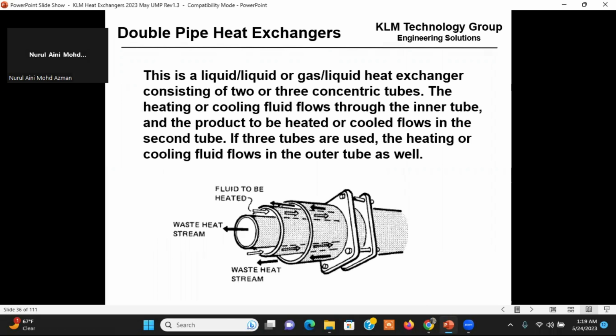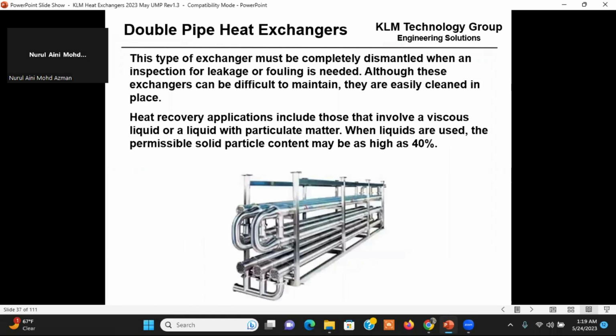A double pipe heat exchanger looks like this. The waste heat stream, the stream that has the heat, is kind of counter current, and it flows in separate pipes. Double pipe heat exchangers are very good when you have high fouling, slurries, and things like this. So they tend to look like this. The negative is they must be completely dismantled for inspection and cleaning.